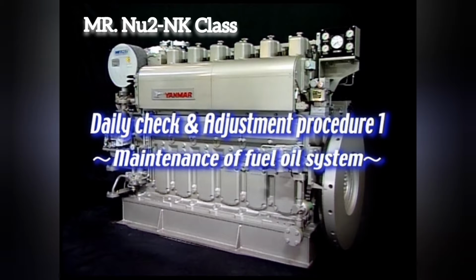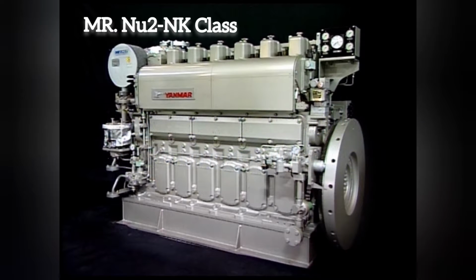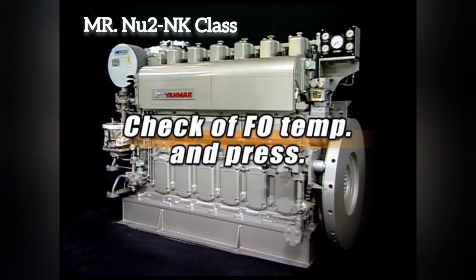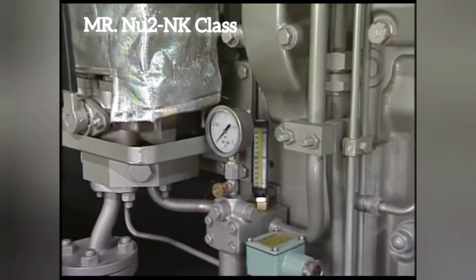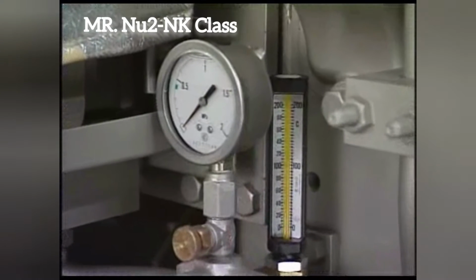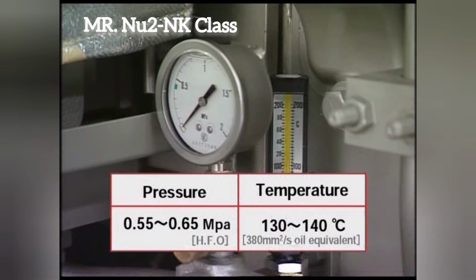In this chapter, I will first explain part of daily maintenance check and adjustment procedures for fuel oil system. While the engine is running, check that the pressure and temperature of fuel oil are within the specified value that you are watching in the video.